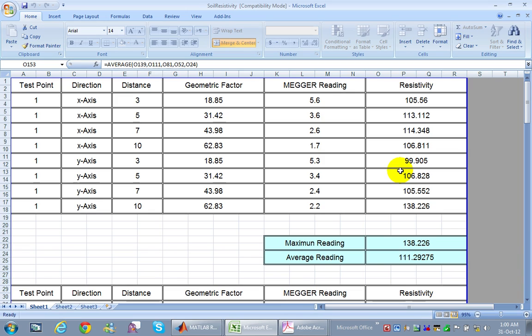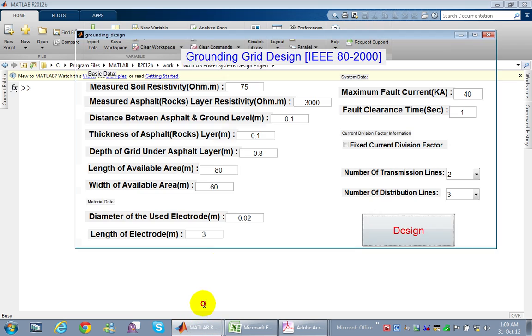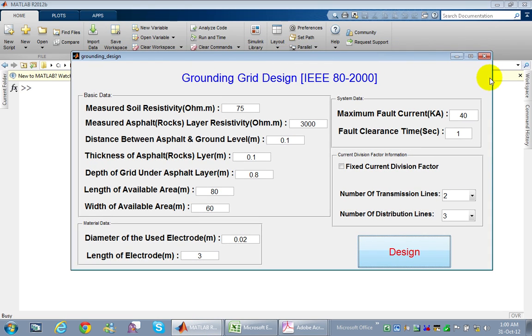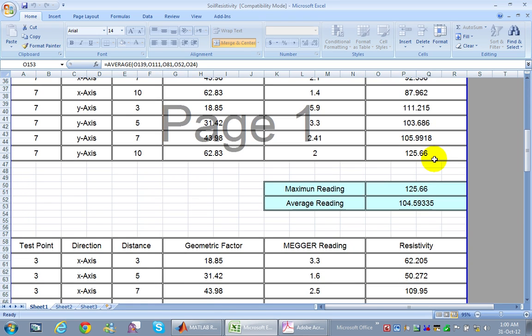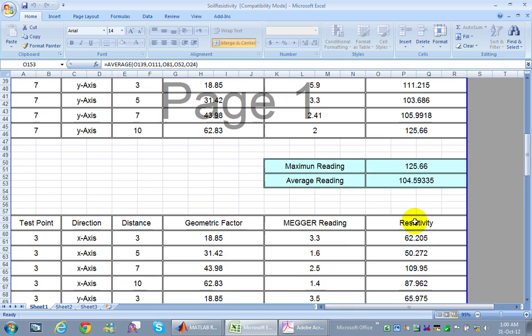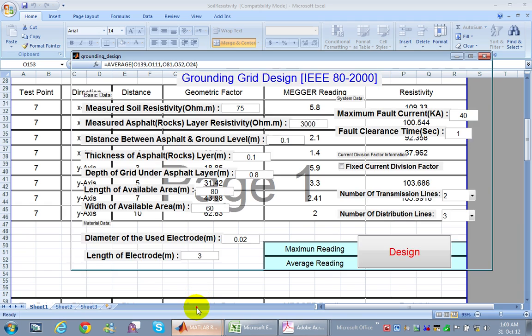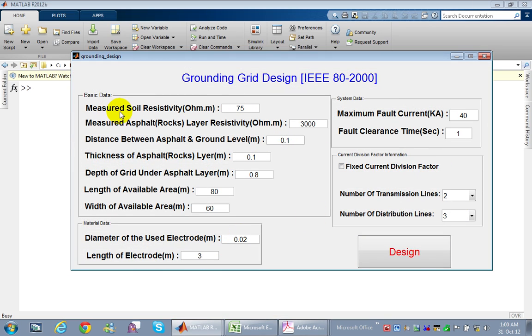After completing the soil measurements, we are ready to start designing the power substation grounding grid. For this purpose I made a custom code using MATLAB. Here is the main GUI window. The first input is the measured soil resistivity in ohm-meter — after taking many measurements at different locations on the substation land, I sum them all and take the average. Here I assume the average is 75 ohm-meter.